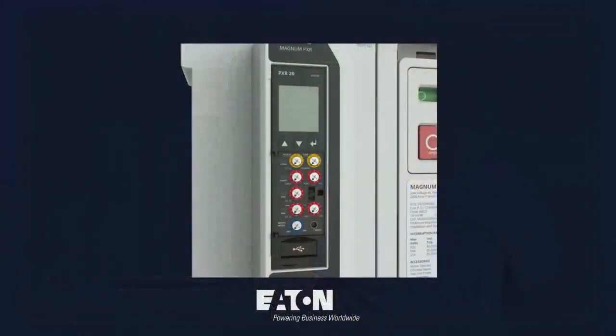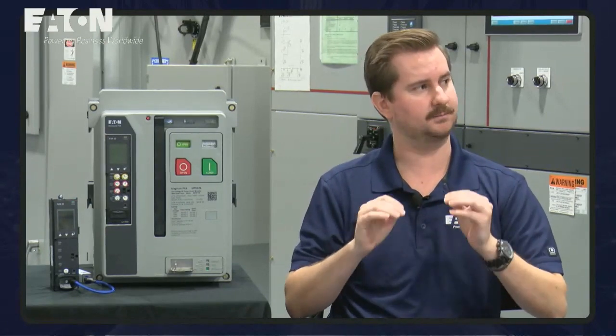Okay, so can you tell us more about how specifically this product, what's in this Magnum PXR that's going to help a customer do that? Yeah, Manny, this is our new Magnum PXR circuit breaker. You can see from the old Magnum with DigiTrip, or Magnum DS, it has a new refreshed look to it. With this, we have our new Magnum PXR trip unit. One of the cool things about it is that it has more accurate metering. Specifically for energy and power, it's accurate to 1%. What that means is you're basically able to use the trip unit as a meter. So you don't have to go and buy an additional meter or other components in order to get that data and be able to see what's going on in the system. That helps reduce cost and footprint, and users can gain insights into what is actually going on to further optimize their system.